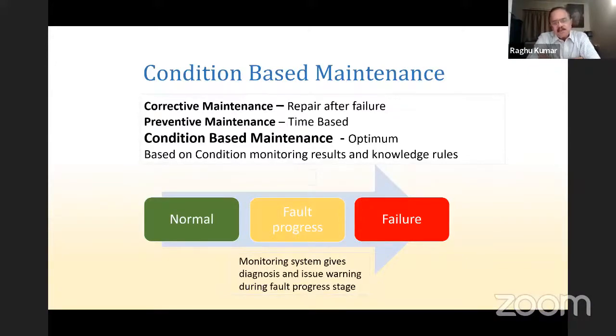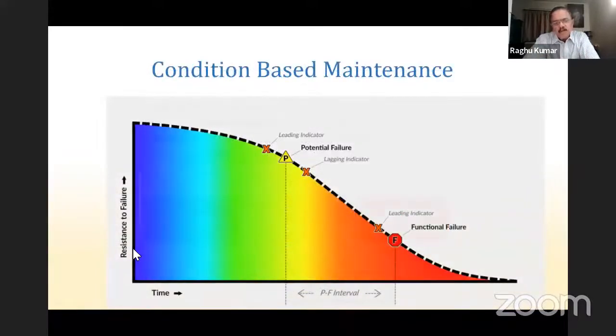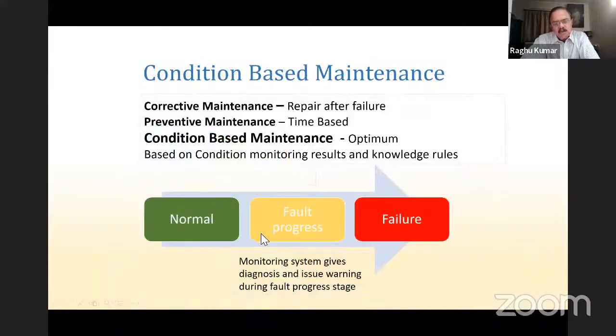Then came condition-based maintenance. The advantage is you have the condition monitoring in place and all the results available, and you attend only problems where the condition monitoring has told us there is some fault which is developing. So these are the three stages for a normal transformer. It moves from a normal stage to a fault progress stage to failure. We have to catch it in this fault progress stage.